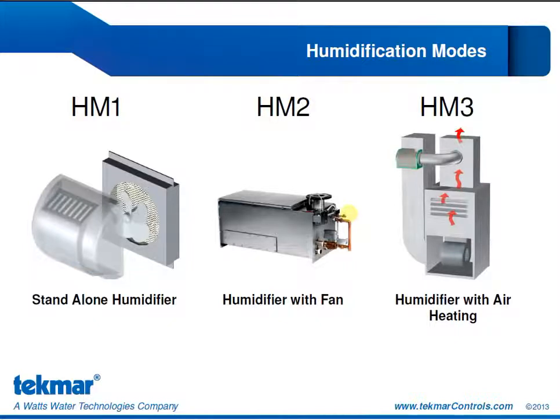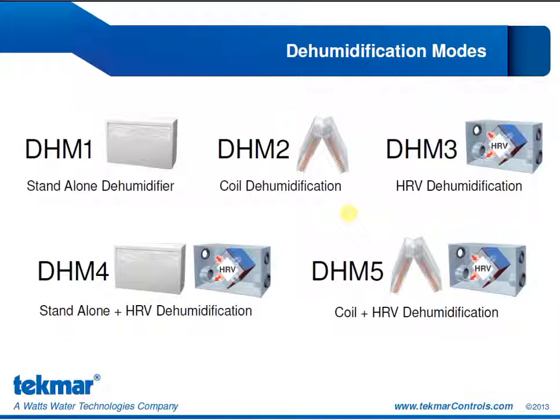The third humidification mode is a humidifier that does require air heating. An example would be a bypass humidifier, where heat from the system bypasses through a wet medium, collects humidity, and then transfers that humidity to the building through the ductwork. This is probably the most popular humidifier, but you are limited by your heating cycles. You cannot operate this year-round.